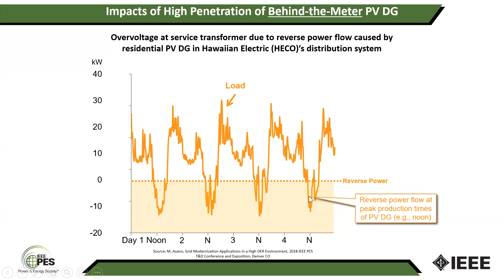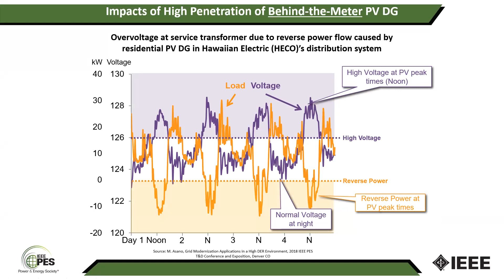When that happens, voltages at that service transformer tend to increase, and there are voltage violations that need to be addressed. Very challenging situation. You can see that voltage increase is perfectly correlated with reverse power flow, or power flow injection from low voltage to medium voltage level.